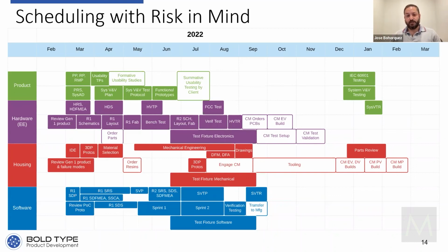And the same thing on the technical front. On the technical front, we try to look at a project and ask, what about this is risky? What might not work the first time around and take 3 or 4 iterations? Is there a way for us to set up an experiment early with a breadboard, with a development kit, with a simple 3D prototyped model, a simple software program, so that we figure out how to do this and make sure that it's going to work before we implement it and go through all of the process and get to the end and then do verification testing and something doesn't pass?